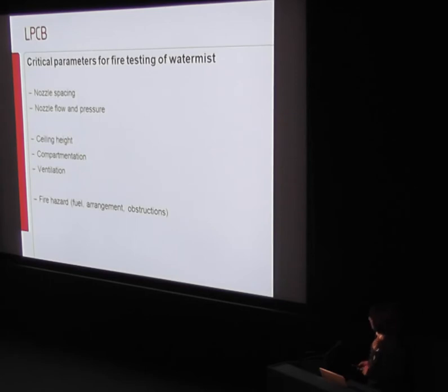So just in summary of our parameter study, which was very much small scale wood cribs. It'd be lovely to have done bigger cribs, it'd be lovely to have done other fuel loads, but we were just investigating the parameters so everybody would have a feel and the data could be available for people to use in the future. Most important: the spacing, pressure and flow.